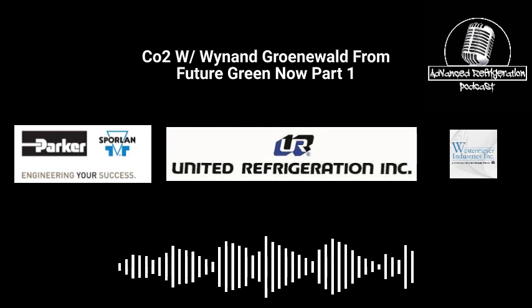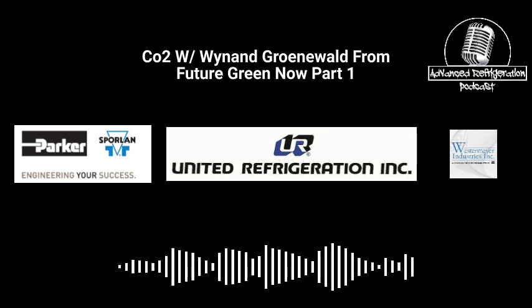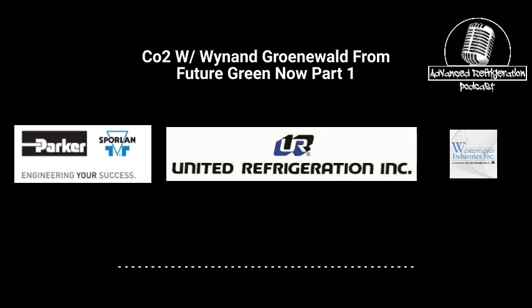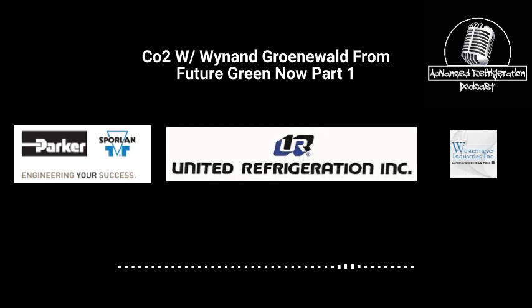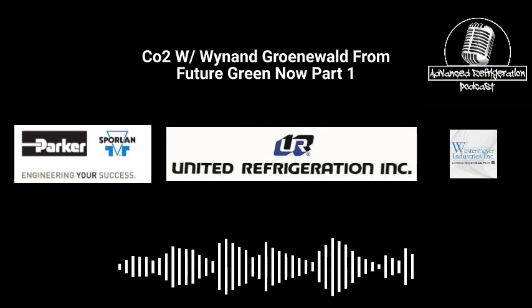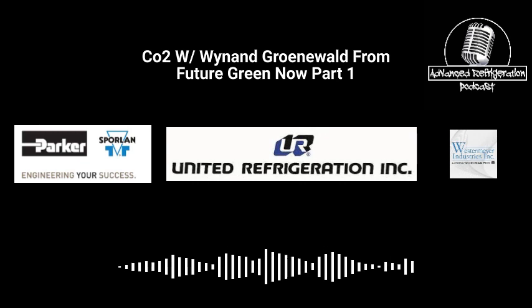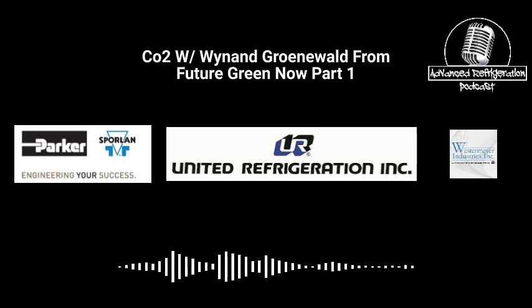Yeah, so as we touched on, I think predominantly our go-to is bottom for liquid, to be honest. Like we discussed, the side is not a problem. There are 2 factors that you need to consider when you look at the piping of the system. Like we said, CO2 is fairly sensitive to pressure drop. The main reason being, no matter what subcooling you gain from your gas cooler outlet or condenser when you're in subcritical mode, as soon as you expand through your high pressure valve, you're basically at a saturated liquid. So if you do not subcool, predominantly we'll see your refrigeration systems either have the flash gas going over the liquid to get some 2K or 3K subcooling out of it. A lot of times you get your superheat out of your LT coming back and use that to subcool your liquid.